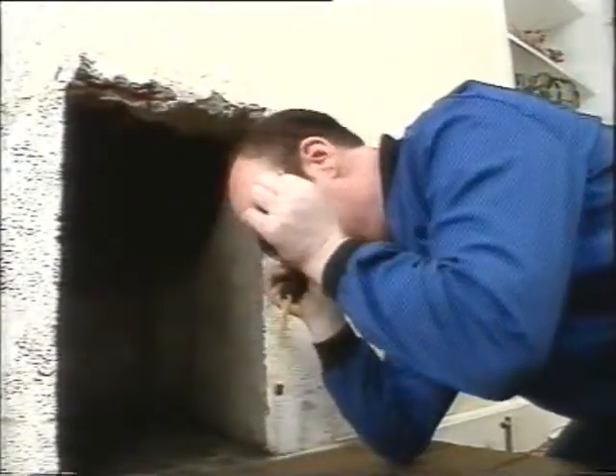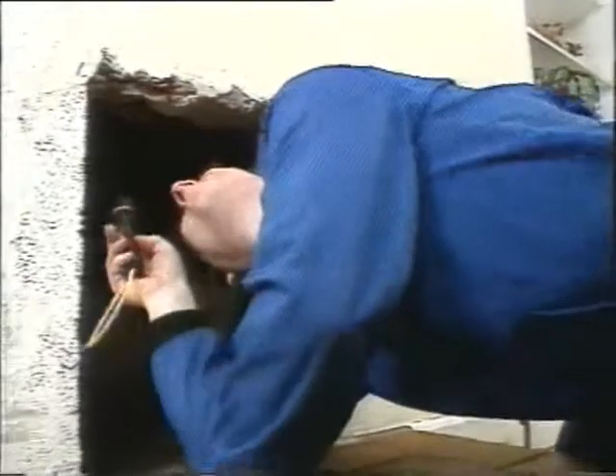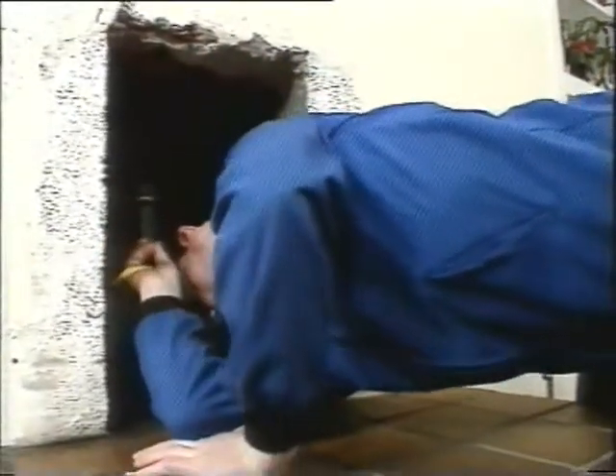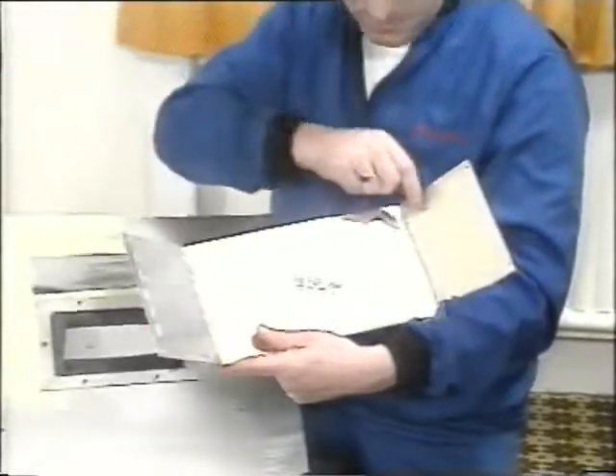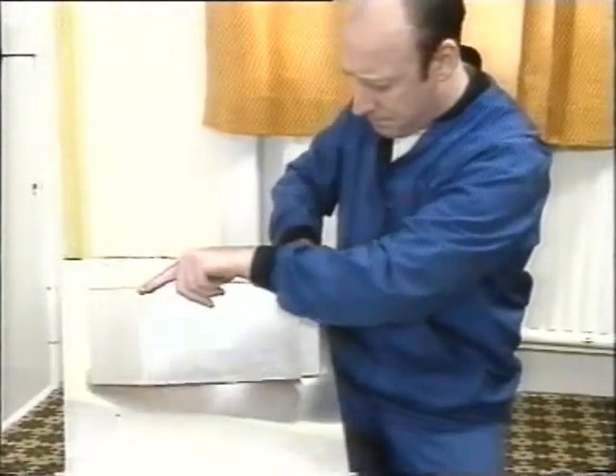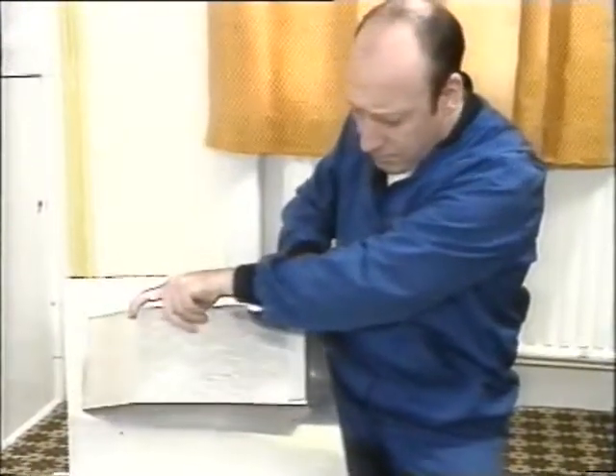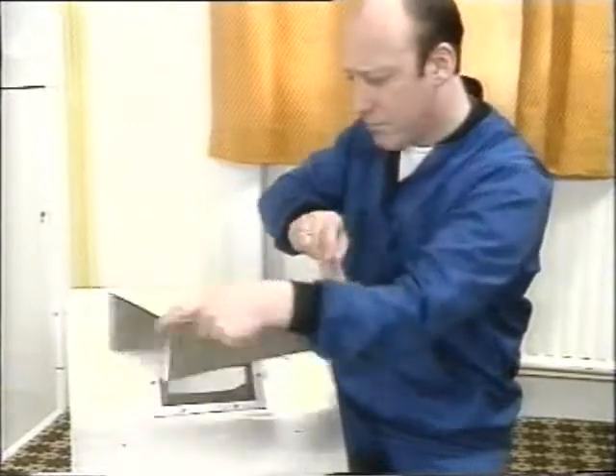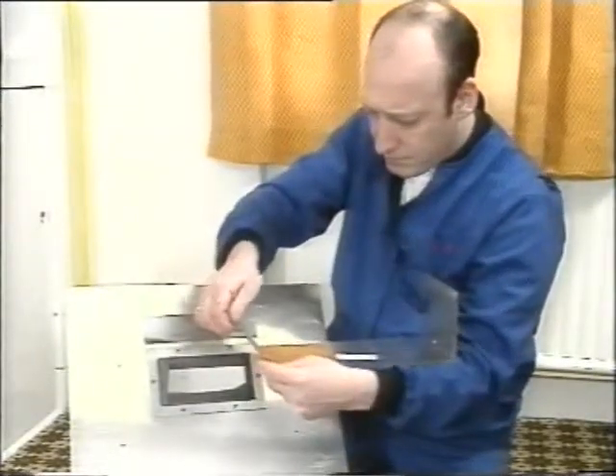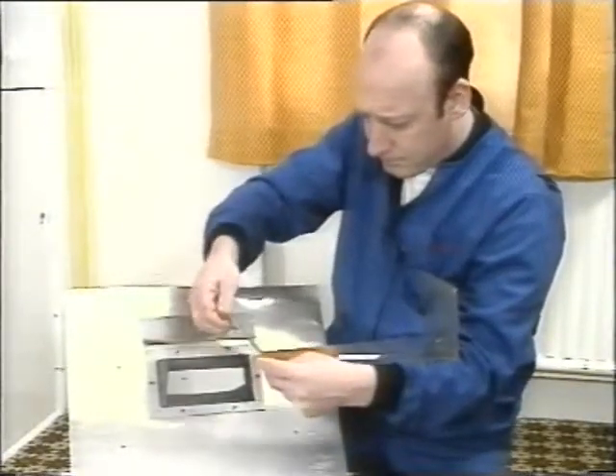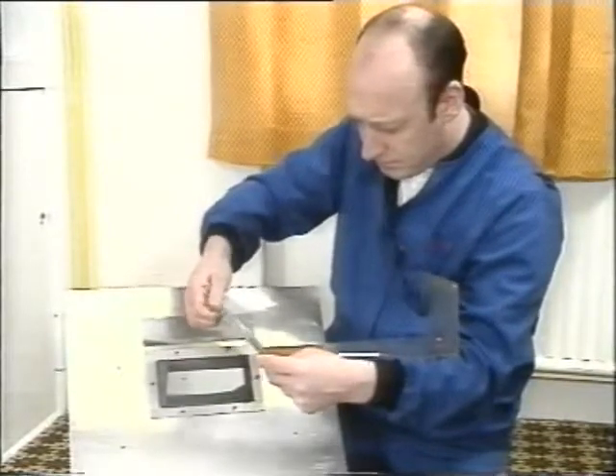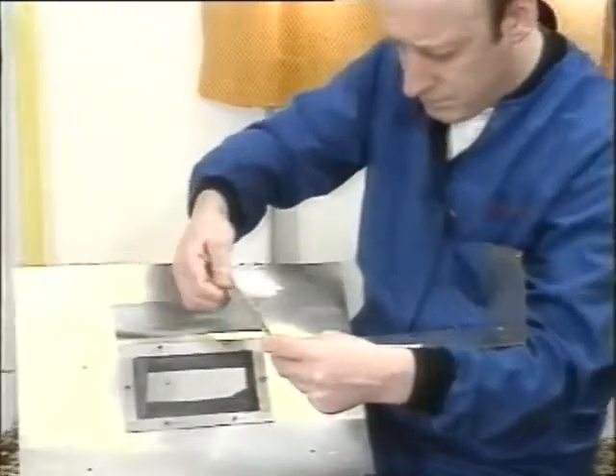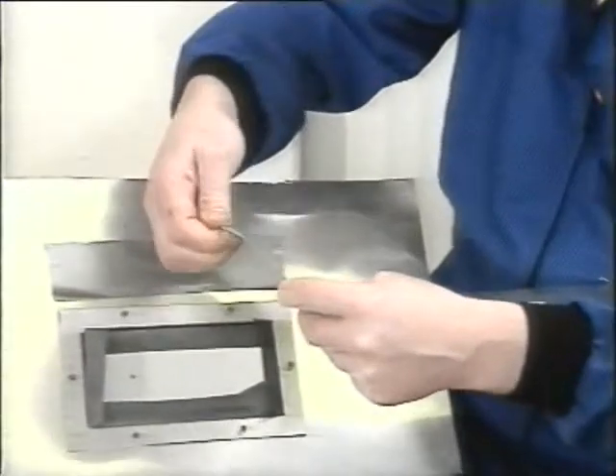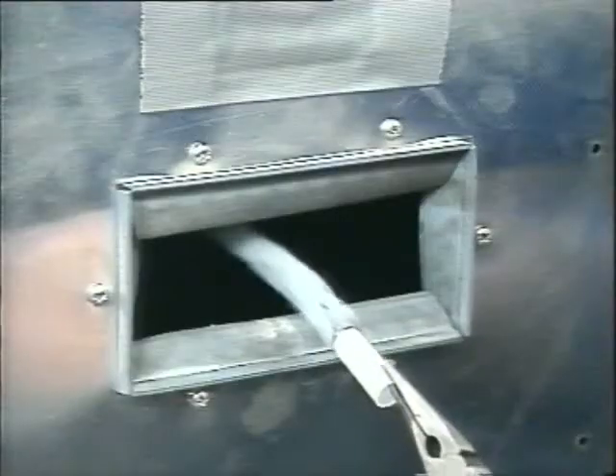And if the chimney has been used previously for an appliance burning some other type of fuel, it has to be swept. If a gas fire is fitted into a precast flue, it could create temperatures higher than 66 degrees Celsius on the flue wall, so you'll have to fit a cooler plate. But before you do, check that the appliance is actually compatible with that type of flue. Not all of them are. The flue pull should be tested at this stage.